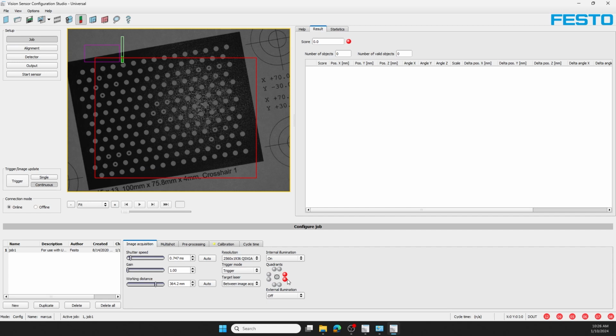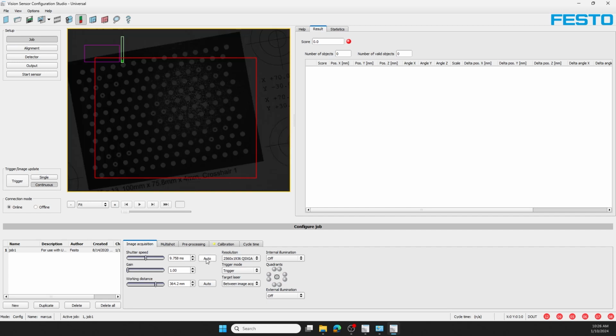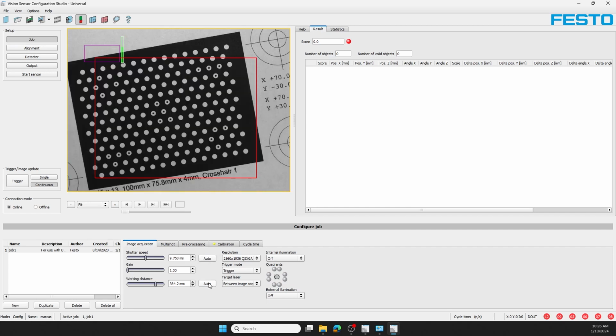I'll optimize my lighting for the room that I'm in. Today I'm just using ambient. Feel free to use your own. And I'll auto set both the working distance and shutter speed. For this calibration, the working distance cannot change once it's set, so either measure it or auto set it accurately.